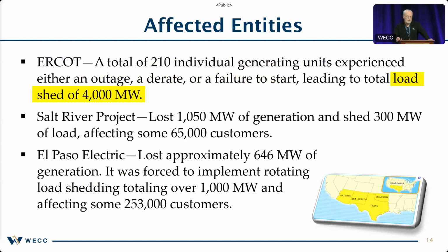So when system operators are operating the power system in real time, their goal is to maintain the power system in a reliable operating state. It's not to keep the lights on for everybody if that's not what works out. Ideally, everybody's lights are on, everybody has the power they need. In a real-time operating condition, if you don't have a balance between your load and generation, then one of the two has to go. If you don't have generation you can bring on, then you have to take load off. Salt River Project, 1,050 megawatts of generation, 300 megawatts of load. El Paso Electric, 646 megawatts of generation, 1,000 megawatts of rotating load shed. About 1.3 million people were impacted by this event as they went through the course of it.